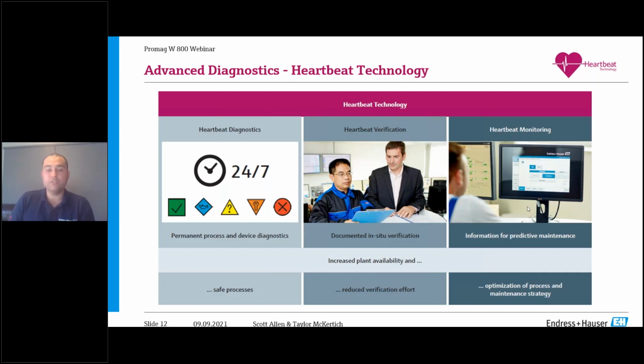Heartbeat monitoring is about using those diagnostics for preventive maintenance. You might monitor, for example in a flowmeter, impedance or resistance values, continually checking to see if they move or drift over time as early warning signs, so maybe you need to do some maintenance. You can use heartbeat diagnostics for that function as well.